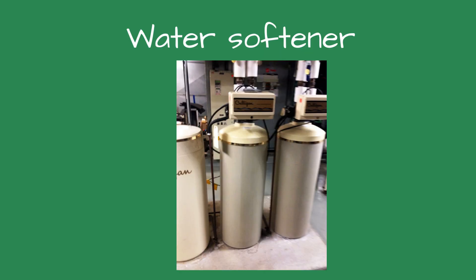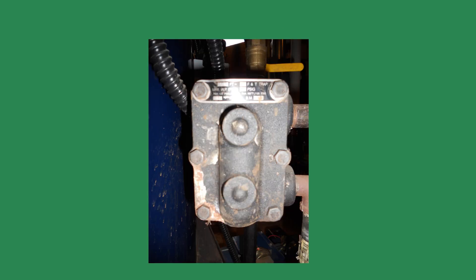Water softener. A water softener is a good idea for a steam system as it will reduce the scale inside the boiler and lower the chemical treatment requirements. High-level spill. When more than one steam boiler is used in a physical plant, the idle boiler will usually flood. If this happens, the boiler may not fire. ASME recommends installing a high-level spill trap about two inches above the normal water line. If the boiler water level rises to that point, the steam trap opens and the water is sent back to the condensate tank, eliminating the chance of boiler flooding.